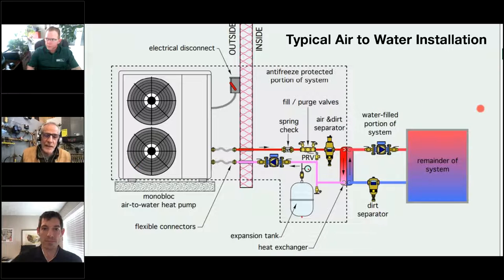Yeah, I'll be honest, I haven't installed one. I wish I had one here in my shop, and I'm working on getting one, but that part I don't know a lot about. Certainly the hydronics and what connects A to B, I can speak to that. So it's going to be piped like a typical hydronic system. We want to have air removal. We want to have dirt removal. We want a good purge point where we can get a good flow through that to get all the big air out so that the air separators can do their work. Spring check valve, not a swing check valve. Always use a spring check valve on hydronic applications.